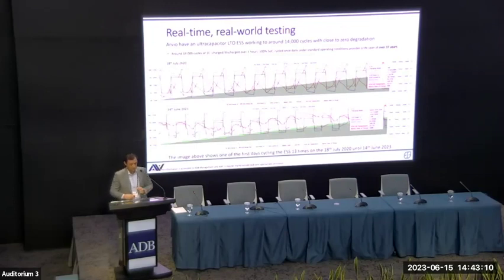These are two snapshots from the dashboard of their test battery, taken when they began cycling around July 2020, and this one from yesterday. They're cycling about 13 times a day at a C1 rate, for over 14,000 cycles. At 2 cycles per day, 14,000 cycles equals about 20 years. They haven't reached 35,000 cycles yet, but it's looking good, showing pretty much zero degradation after 14,000 cycles.